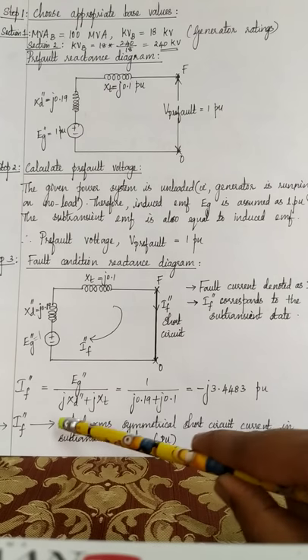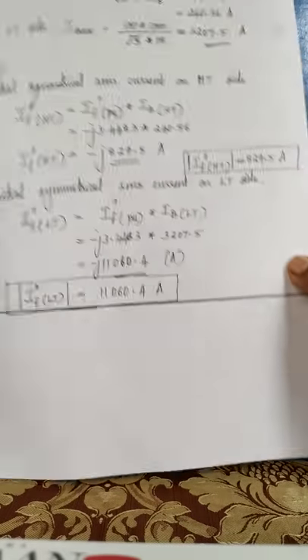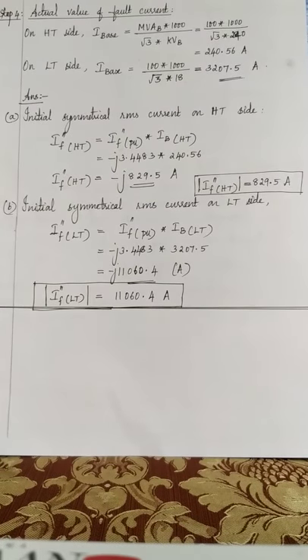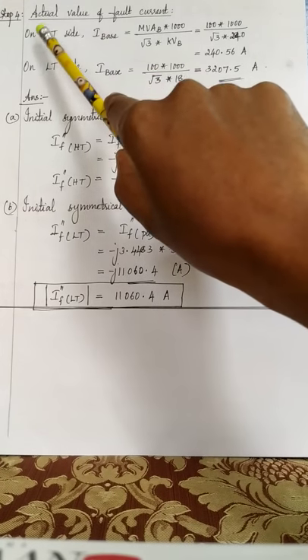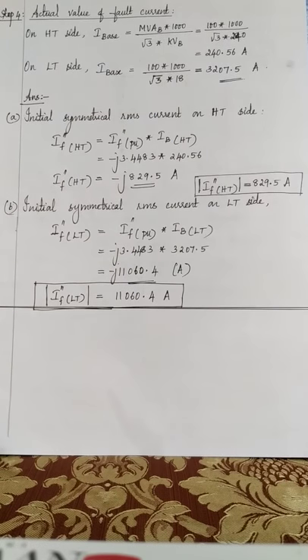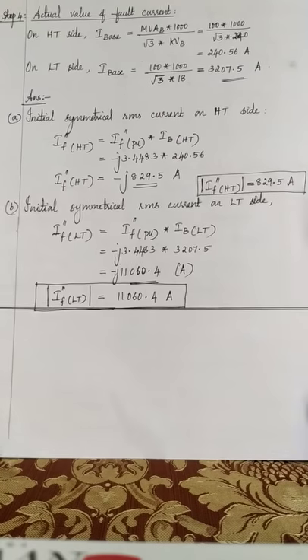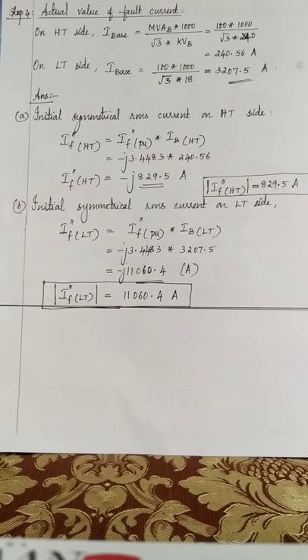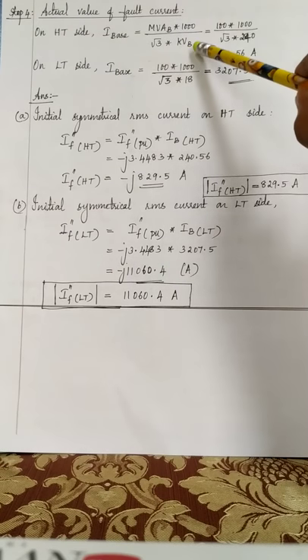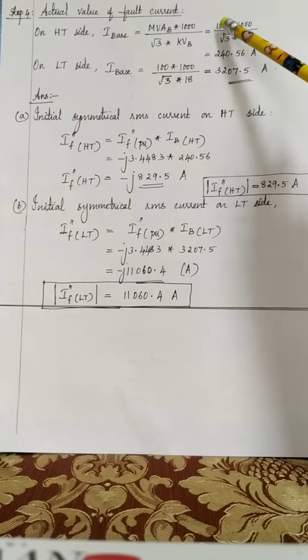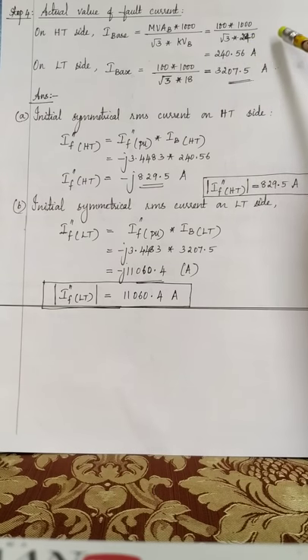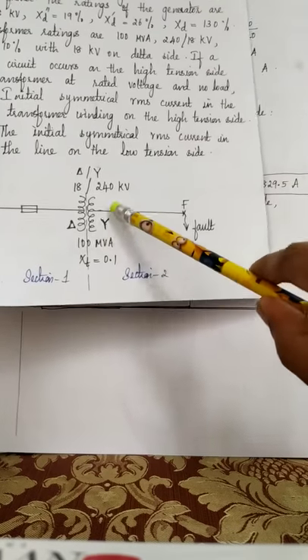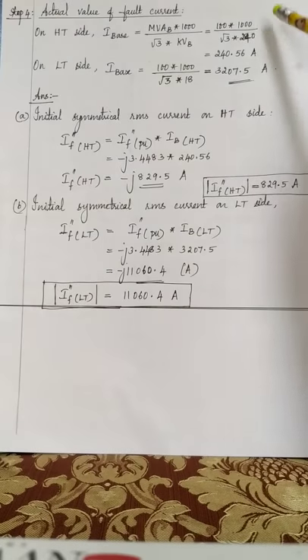Okay. So now what is asked? You have to find out the RMS values of the initial symmetrical fault current on the HT side, and part B is on the LT side. So step 4, find the base current on the HT side and the base current on the LT side. Base current on the HT side is MVAB into 1000 by root 3 KVB on the HT side. What is the HT side MVAB? 100. What is the HT side KVB? It is 240. HT side, section 2, is 240. You will get the base current.